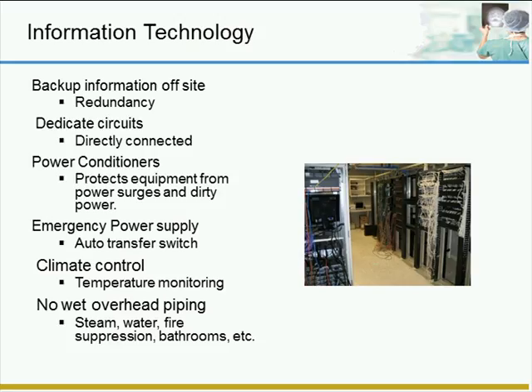Yeah, with regard to that last point, Bill, and no wet overhead piping, management should be aware of the location of any water sources on the floor or floors above the server rooms or other rooms that might contain delicate electronic equipment. Many new construction projects are specifying a physical barrier similar to a rubber roof membrane, which is applied directly above the ceiling of these locations. In these instances, we also need to consider any sprinkler piping that is in or above the room. For protection of server rooms, we should consider wet pipe sprinkler alternatives such as FM200 or other clean agents, or possibly dry pipe valves, pre-action systems, or a combination of all of the above.